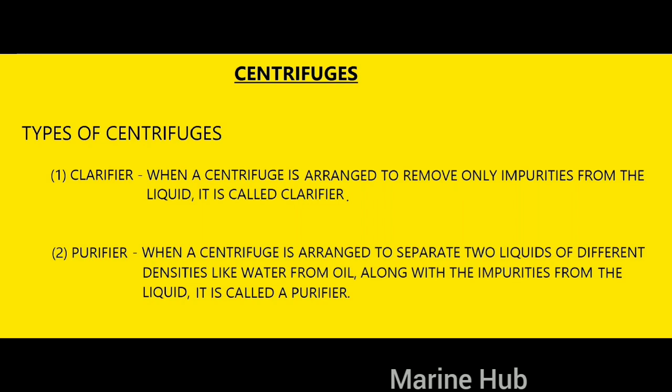Clarifier is an arrangement to remove only impurities from the liquid. Purifier is an arrangement to separate two liquids of different densities like water from oil, along with the impurities from the liquid.